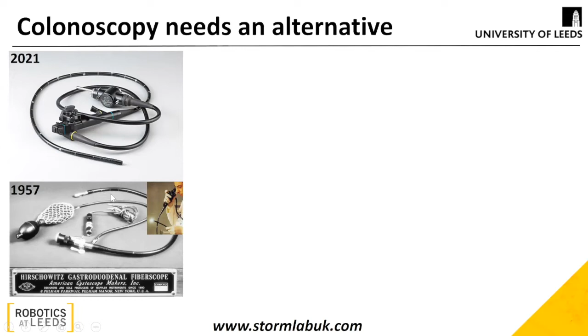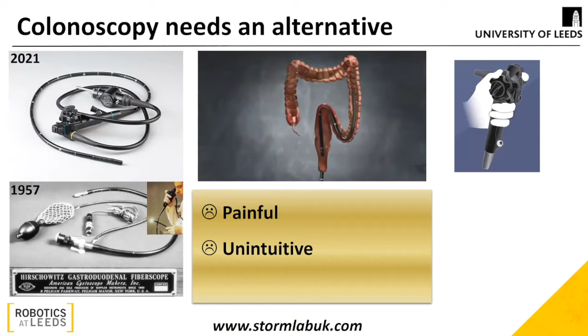The first being pain. The flexible endoscope is designed to be introduced from its proximal end, and as such, the distal part needs to interact with the surrounding tissue to advance. So when a bend is approached, the instrument must, by design, stretch the tissue to progress forward. This causes pain in the patient and increases the risk of perforation. Then the user interface is highly unintuitive, with the thumb controlling 2 degrees of freedom and the other hand used to move the endoscope forward and backward. And finally, the instrument is extremely expensive by design, with all its integrated components.